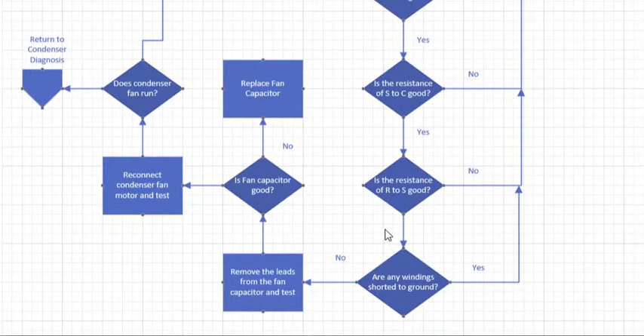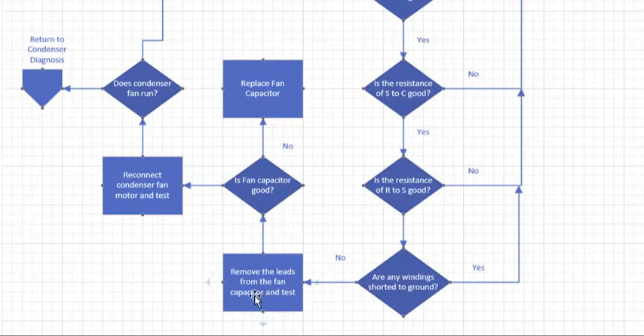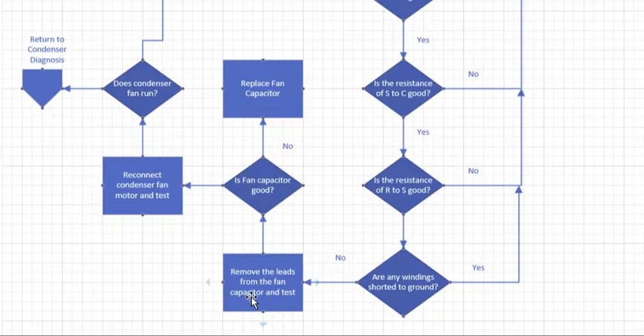If everything else tests out good on the motor windings, go ahead and remove the leads from the capacitor and test the capacitor. As you're removing leads, make sure you know where they go. One of the best ways to do this, take a picture with your cell phone so you always get the leads back in the correct place. Or look at the schematic and make sure it's wired properly to start with.